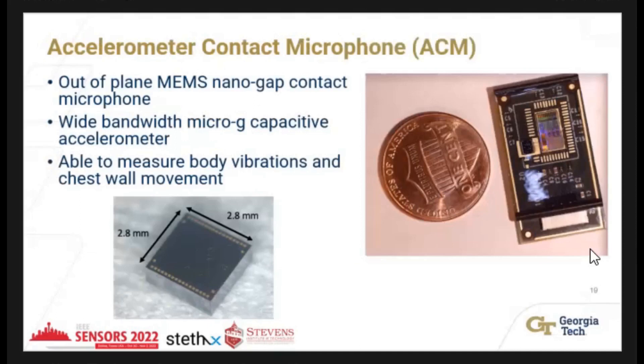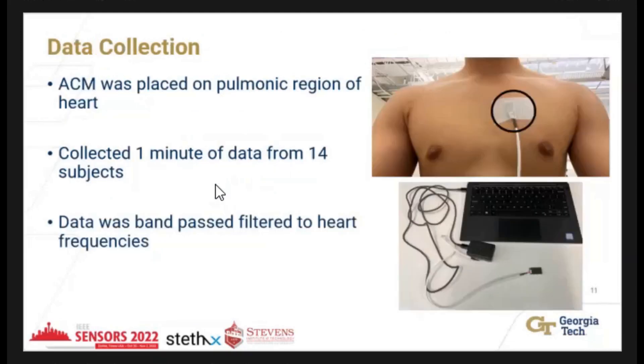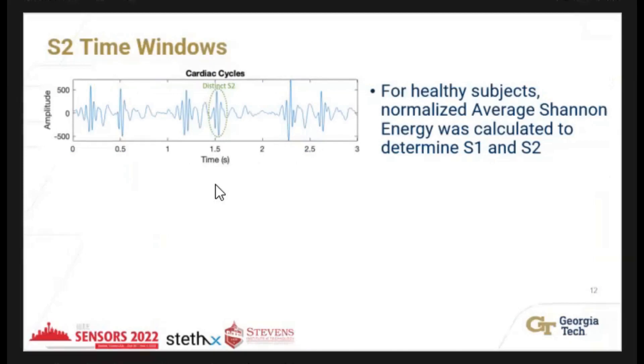Our lab at Georgia Tech has created an external contact microphone, also known as the ACM, which is an out-of-plane MEMS device. It contains a wideband MEMS capacitive microphone accelerometer. Because we're capturing micro-g accelerations, we can actually measure body vibrations — such as heart sounds and chest wall movement — allowing us to know when the patient is inhaling or exhaling. The ACM was placed on the sternal region on 14 subjects: 10 healthy subjects with varying BMI and 4 subjects with known heart disease such as aortic stenosis. After collecting data, we bandpass filtered it to the major heart frequency range of 60 to 200 Hz.